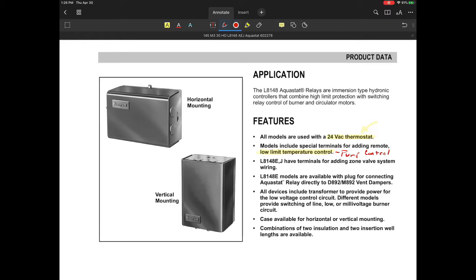I remember some of the earlier Aquastats that I dealt with that didn't include the relays. They actually had a separate high limit and a separate low limit built into the same unit, and then you had to wire it up using relays to make these work. So additionally, let's take a look at the models that are the L8148 E and J. They've got terminals that basically allow you to have zone valve control system wiring on there. There are some that don't, some that do. With the E model, you can also plug in a vent damper.